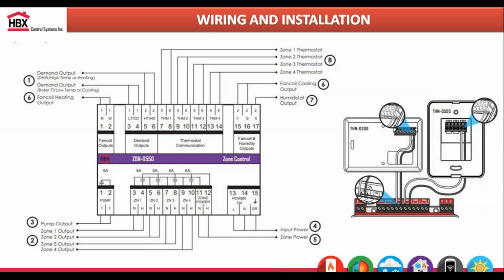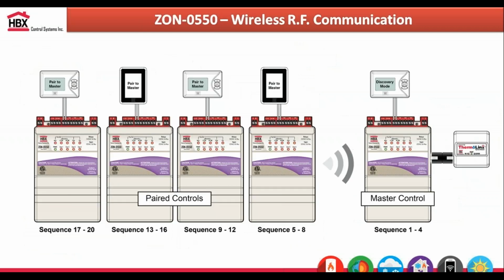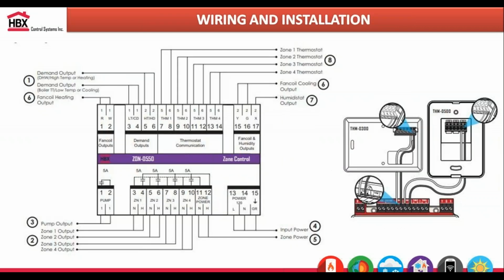All your thermostats also get connected at the top of the zone controller. You can use our THM 500 or THM 300, which we'll talk about in the next couple of slides. The real nice thing in terms of wiring is that for those stats, there are only 2 wires back to the zone controller, so it's just power and communication. You don't have to put 24 volts to these stats. It's getting its power from the zone controller and communicating back to the zone controller, so we call it a communicating stat with the Zone 550. You can do up to 2 stages of heating and 2 stages of cooling, and provide humidity control off those 2 wires. That makes it really perfect for retrofitting older homes. If you want to update those homes, you don't have to put in any new infrastructure in terms of wiring for the thermostats, which is real nice.